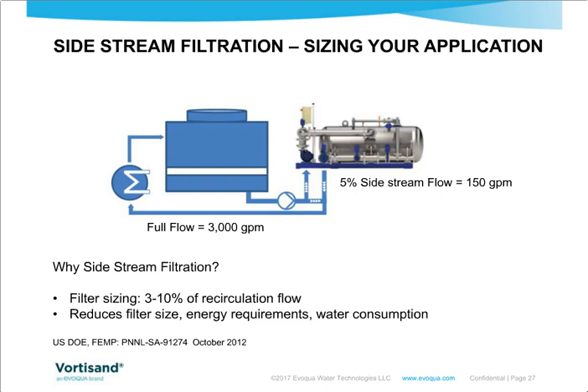And you can see just to the bottom right of the cooling tower, you have this pump that then pumps a small side stream through a fine filtration filter. In this case, we designed a 5% side stream flow, calculating to be 150 GPM versus the full circulation flow of 3,000 GPM. And the typical industry rule of thumb is that anywhere between 3 to 10% of that recirculation flow can allow you to properly remove all those small particulates over the course of a number of weeks or months. And this is different. You're not one-pass filtering. You're not taking that full 3,000 GPM and running it through the filter constantly. You're taking a small slipstream, and over the course of many weeks or months, you can achieve that removal rate of removing those small particulates less than 5 microns.